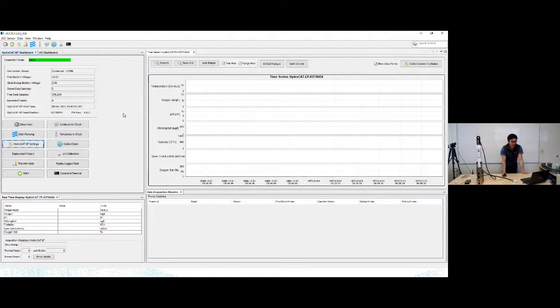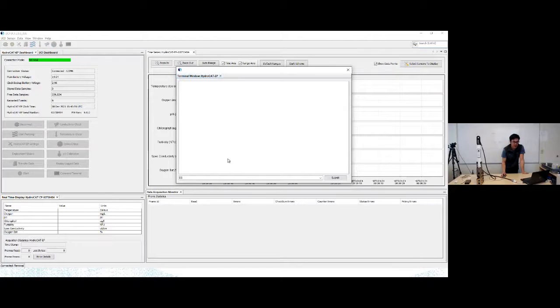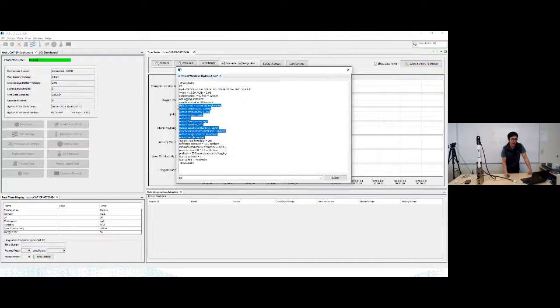That's just one of many options we have here. One thing I also like is the command terminal. When you click on that, you're going to have this little window that is pretty similar to basic terminal software. This is where you can send terminal commands directly to the instruments if that is more your speed. We can send things like the DS command to get the status. That's going to give us a full rundown of battery voltage of our instruments, what parameters we are outputting, how many samples we have in the memory, how much space we have for sampling, and other valuable information like our serial number, the current date and time of the instruments, and our minimum conductivity frequency. There's a list of commands at the end of the HydroCAT EP manual. I recommend looking at that to learn what kind of stuff you can do.